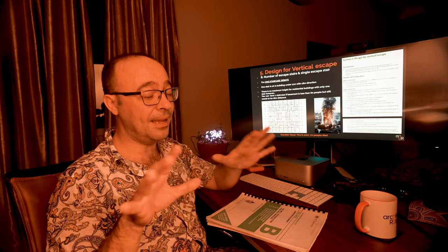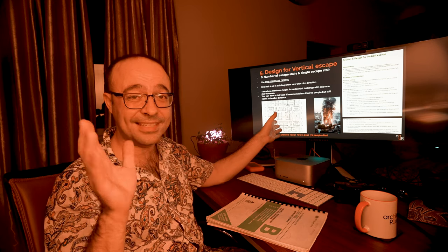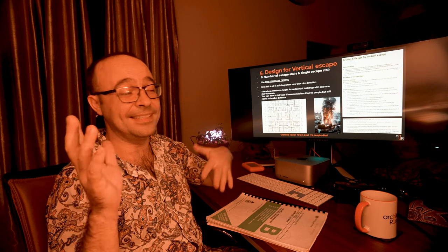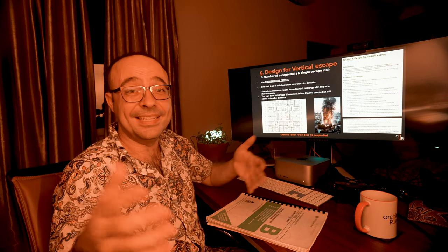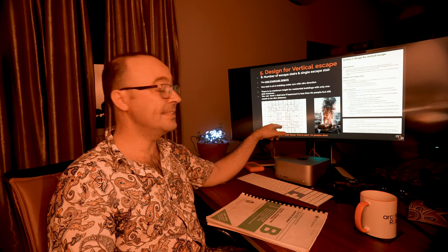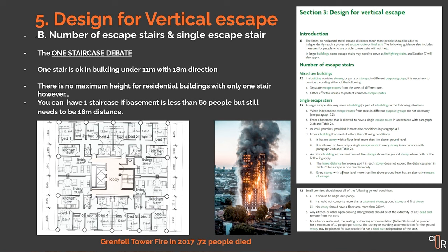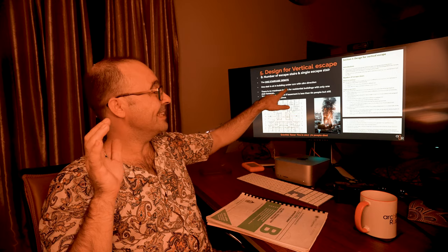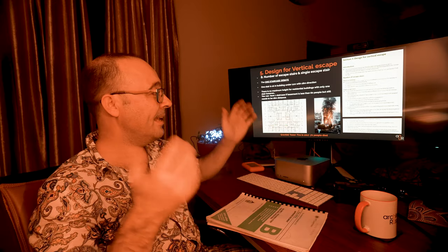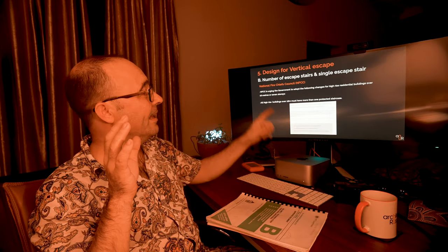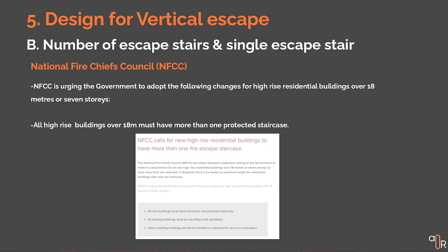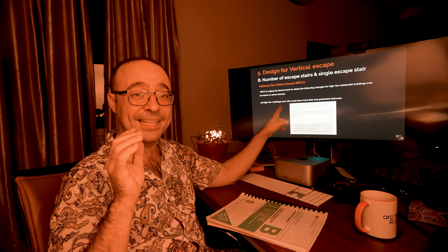Now the number of escape stairs. There are some countries that allow one escape stair in high buildings, but I wouldn't recommend it. Anything above 18 meters, definitely put another escape stair. It's not a complete law in the UK, but some countries like Canada require a second escape stair over a certain height — I think Canada is only like three storeys. This happened at Grenfell Tower, which had one escape stair, and they're trying to change that rule now. The National Fire Chief Council is writing to the government recommending two staircases in all buildings above 18 meters.